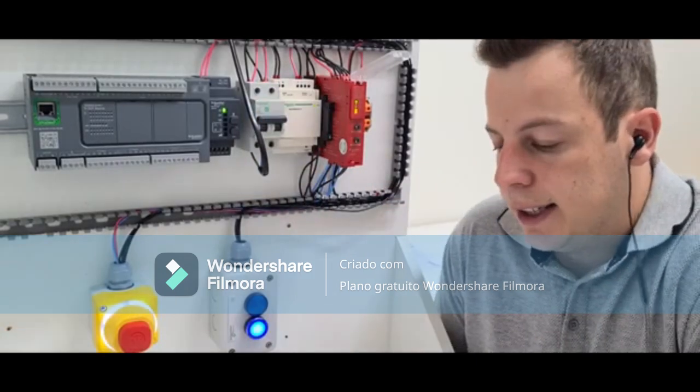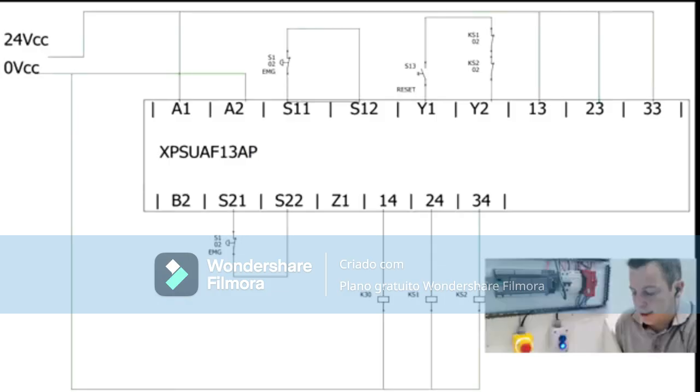Now an example connection on the bench. My application here is an emergency button with two closed contacts and a reset button. Terminals A1 and A2 are the power supply: 24V positive and negative. The control signal exits S11, goes to the emergency button, leaves one contact of the emergency button, and returns on S12 — that is what monitors whether the emergency is activated.